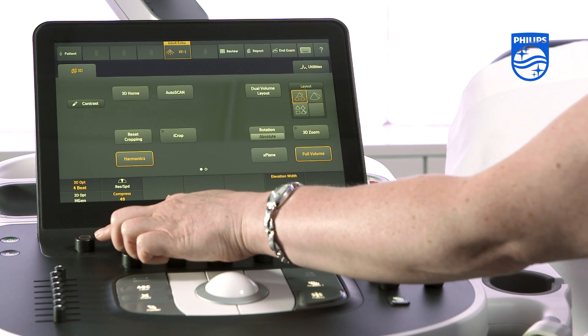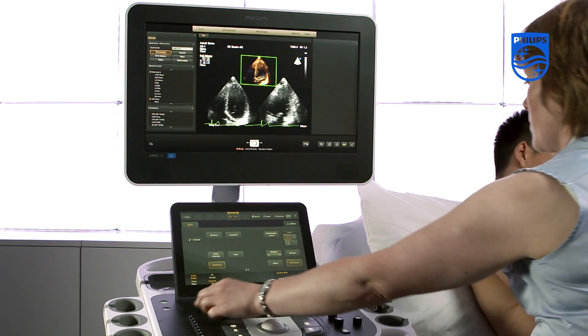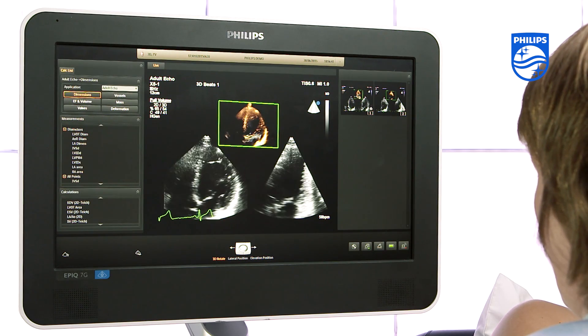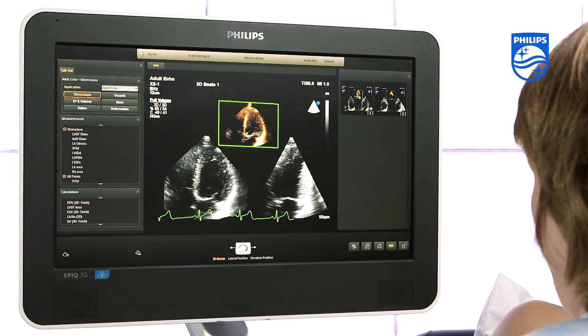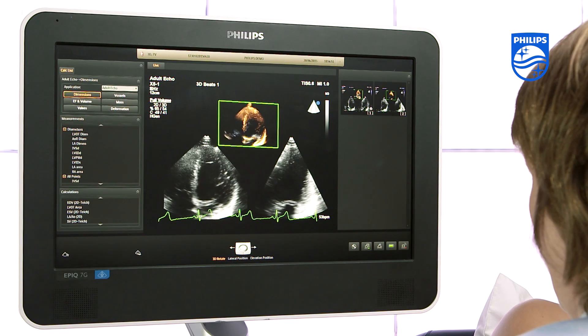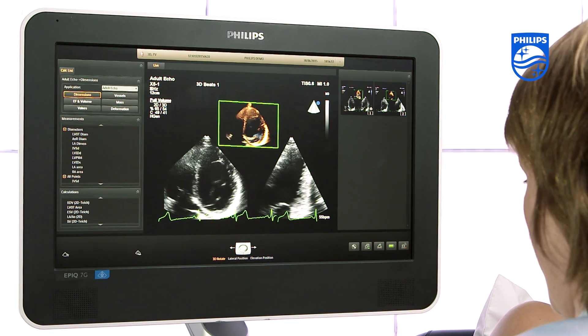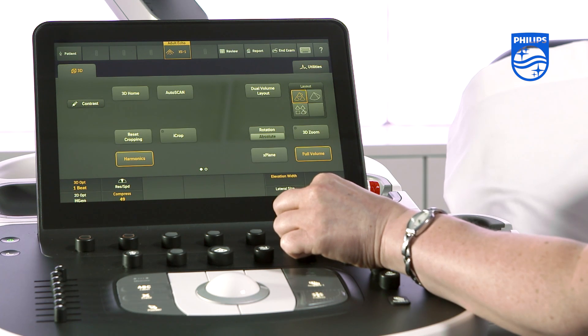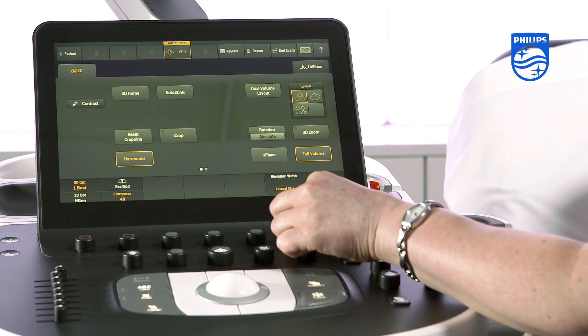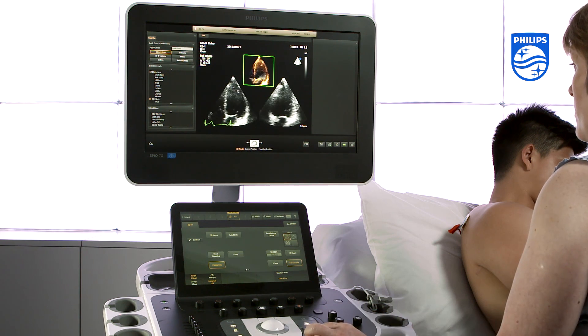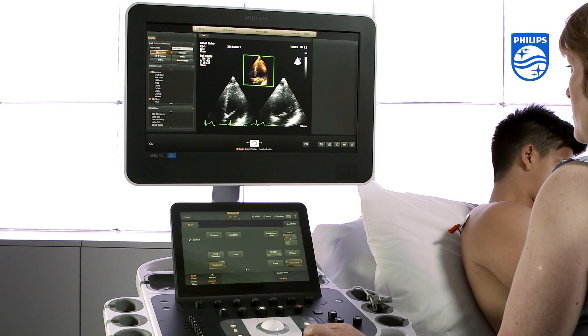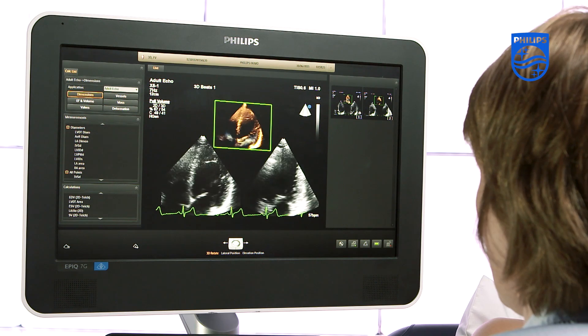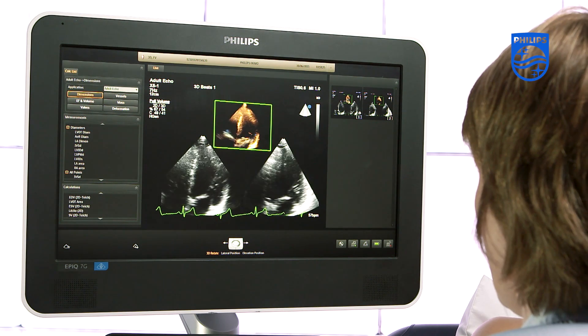Turn the 3D Opt control to one beat as you will find it easier to adjust your target volume size and position. Here we have the cropped zoom volume plus the lateral and the elevation views. Use the elevation width and lateral size controls to adjust your target volume size. You can expand the volume up to 90 degrees in the lateral and 104 degrees in the elevation, so you can accommodate most large hearts.